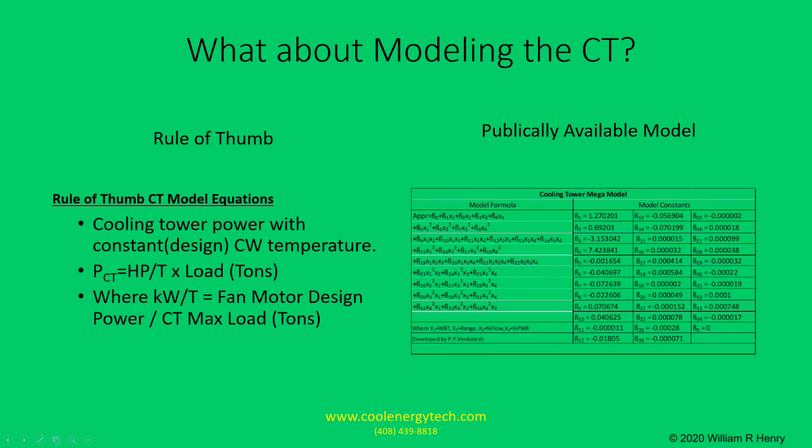For measurement and verification of the cooling tower, we can choose a simple rule of thumb model, such as the one used by York Calc, or a more complicated, time-consuming model. The Department of Energy has their cooling tower model, but there is a potentially simpler model that is publicly available. This is the Venkatesh model, shown here on the right. It is a polynomial equation with 35 terms. Still, when I ran this one on my desktop, it took about 24 hours to complete.